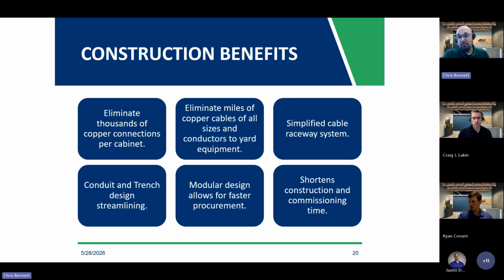Cable raceway systems are greatly simplified because now I do not have hundreds of cables running from the yard back in. So yard interface boxes may be beneficial. They may not even be required at this point. Conduit and trench will not be as big as in traditional design because we do not have that many cables running back and forth. And just in general, the setup and the construction of this system allows for basically set and drop type construction configurations when the station is being built.